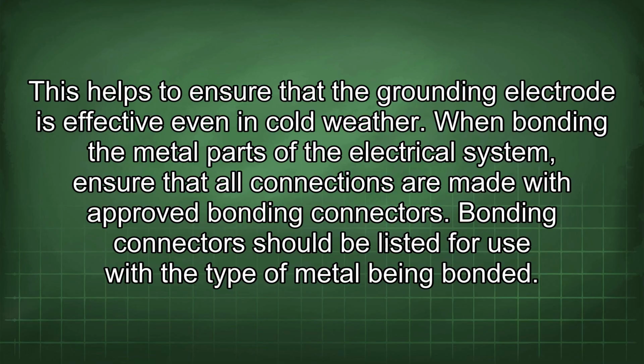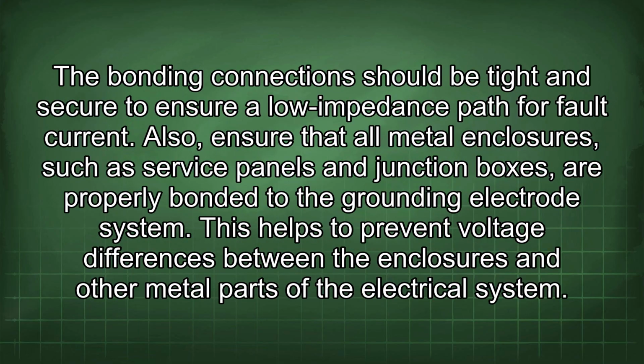When bonding the metal parts of the electrical system, ensure that all connections are made with approved bonding connectors. Bonding connectors should be listed for use with the type of metal being bonded. The bonding connections should be tight and secure to ensure a low impedance path for fault current. Also, ensure that all metal enclosures, such as service panels and junction boxes, are properly bonded to the grounding electrode system. This helps to prevent voltage differences between the enclosures and other metal parts of the electrical system.